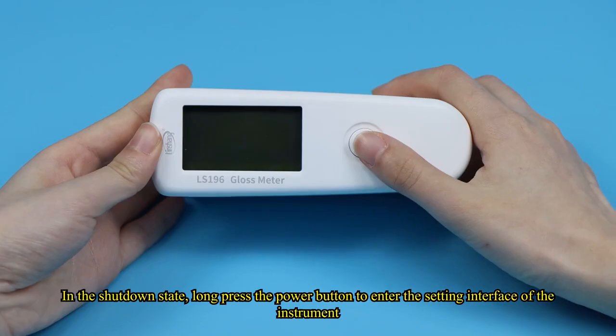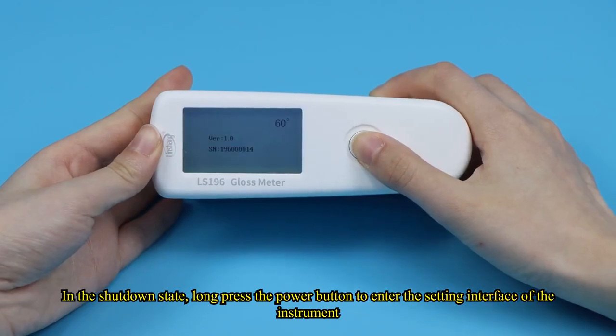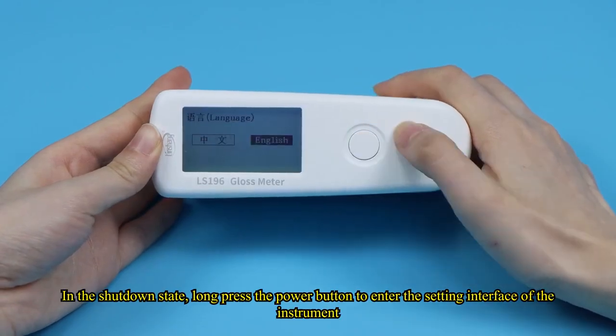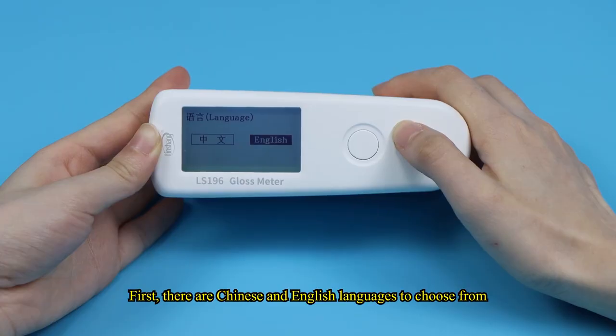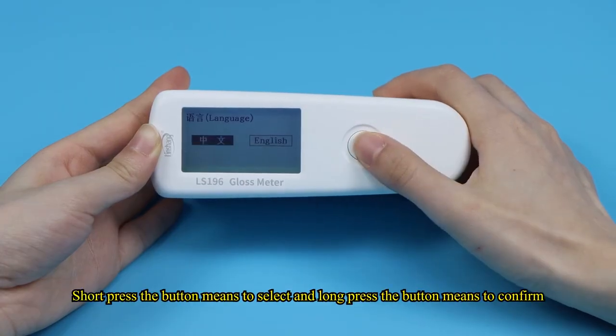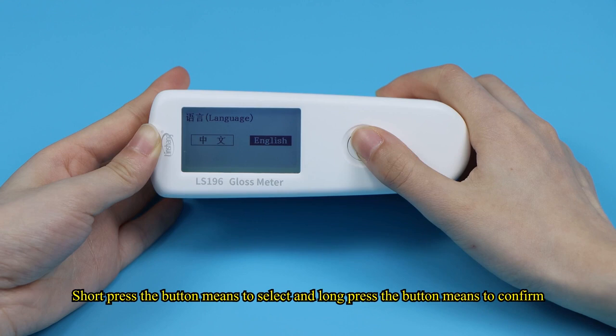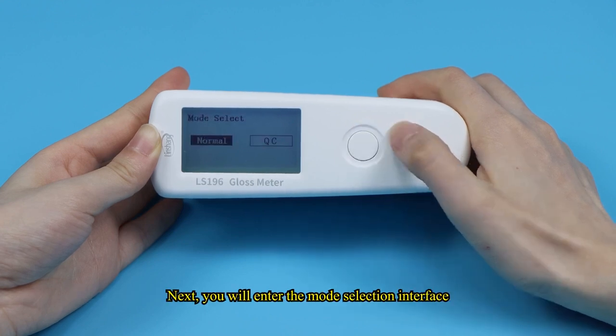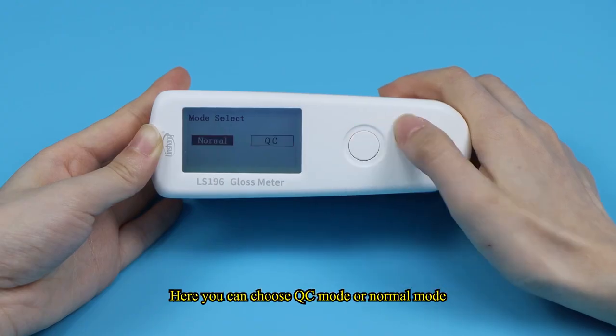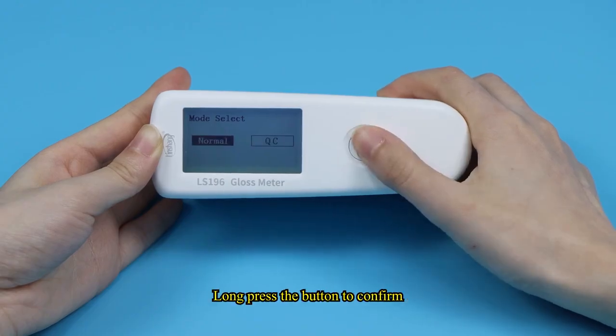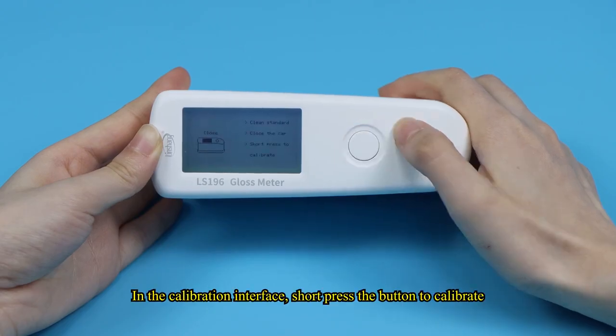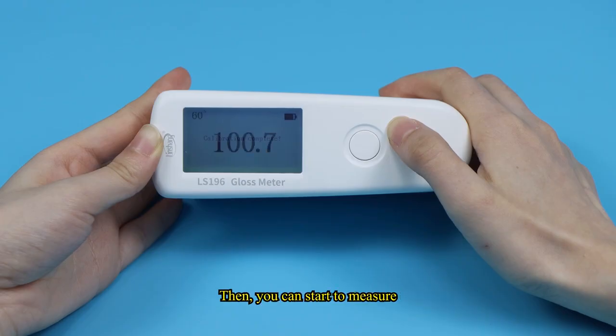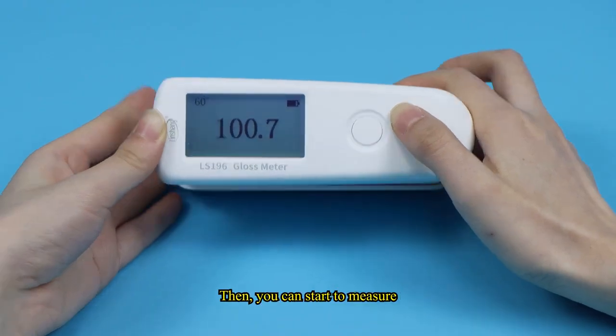In the shutdown state, long press the power button to enter the setting interface of the instrument. First, there are Chinese and English languages to choose from. Short press the button means to select and long press the button means to confirm. Next, you will enter the mode selection interface. Here you can choose QC mode or normal mode. Long press the button to confirm. In the calibration interface, short press the button to calibrate. Then, you can start to measure.